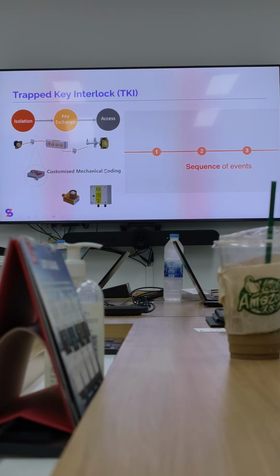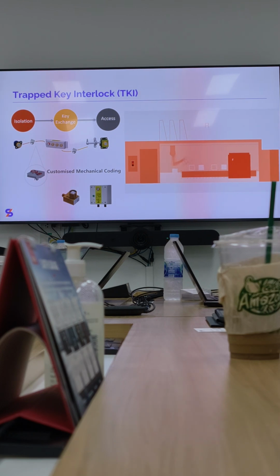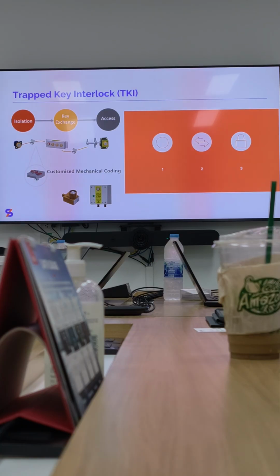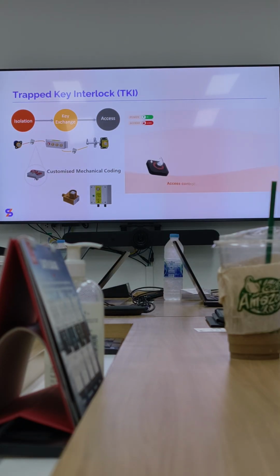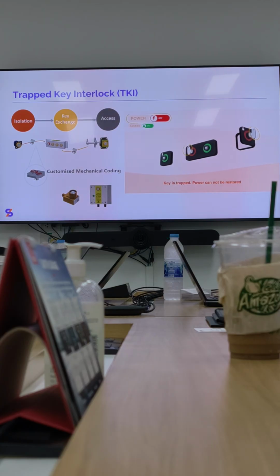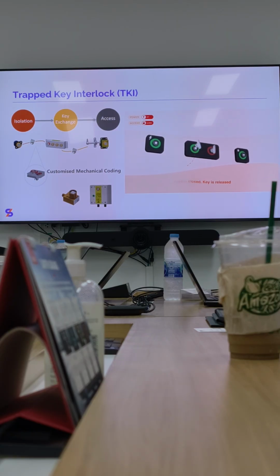Each time a procedure is performed, this ensures access to hazardous or dangerous areas is only permitted once any risk is mitigated. A three-stage process: isolate the power, transfer the keys, and safely access the hazardous environment. Cannot be bypassed and mitigates the risk of human error. Access to the hazard is controlled by a trapped key interlock. The key is trapped and cannot be removed when the hazard is present. To gain access safely, the key must be turned, engaging the interlock with the equipment and isolating the power. The key is then transferred to the access panel or gate, allowing safe access to the hazardous area. The key remains trapped in position while access to the environment is required. The key cannot be released while access is available, and the power source cannot accidentally be turned on while the key is trapped. Once the door or access area is closed, the key is released and can be returned to the power source, which can then be activated.